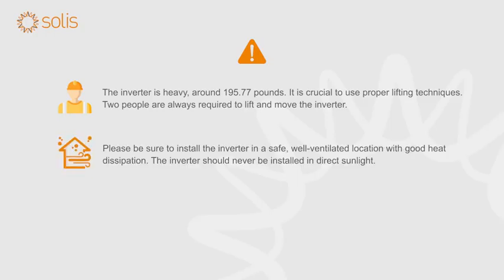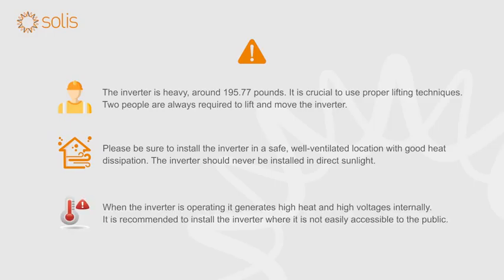Please be sure to install the inverter in a safe, well-ventilated location with good heat dissipation. The inverter should never be installed in direct sunlight. When the inverter is operating, it generates high heat and high voltages internally. It is recommended to install the inverter where it is not easily accessible to the public.